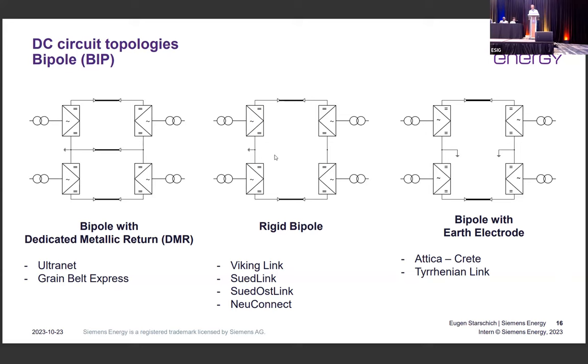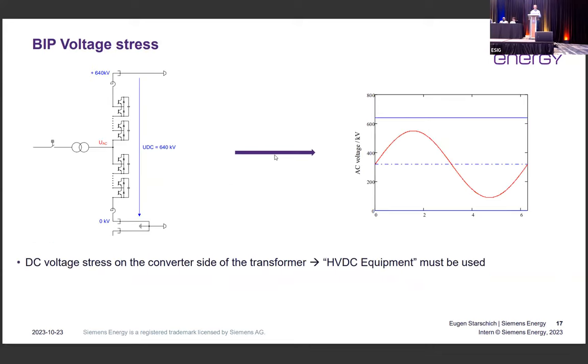Looking at this bipolar configuration, we have the same picture as we have seen before. We want to have the same DC voltage of 640 kV. In the bipolar, we always have an earthing system, so one part is around 0 kilovolts and the other one in this application will be 640 kV. What does it mean? For bipolar systems, we need a higher voltage rating of all the DC equipment. Right now, we are not using 640 kV, but we are using 525 kV.